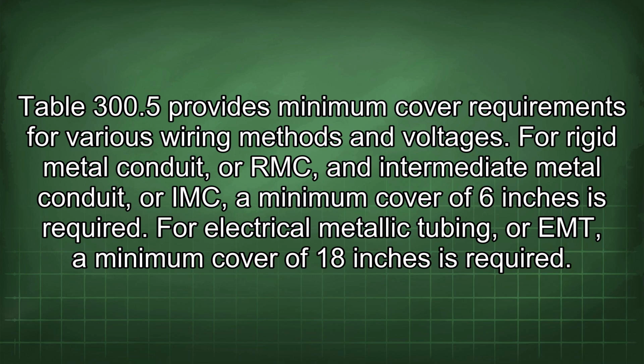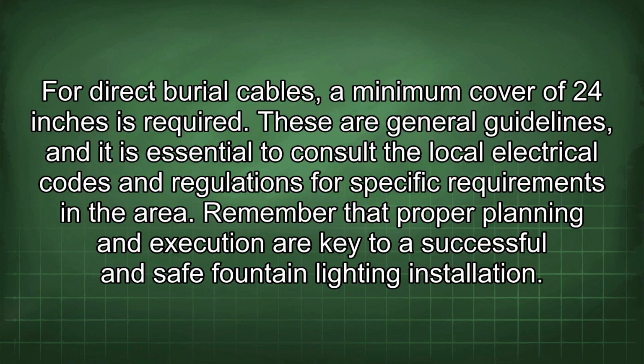Table 300.5 provides minimum cover requirements for various wiring methods and voltages. For rigid metal conduit, or RMC, and intermediate metal conduit, or IMC, a minimum cover of 6 inches is required. For electrical metallic tubing, or EMT, a minimum cover of 18 inches is required. For direct burial cables, a minimum cover of 24 inches is required. These are general guidelines, and it is essential to consult the local electrical codes and regulations for specific requirements in the area. Remember that proper planning and execution are key to a successful and safe fountain lighting installation.